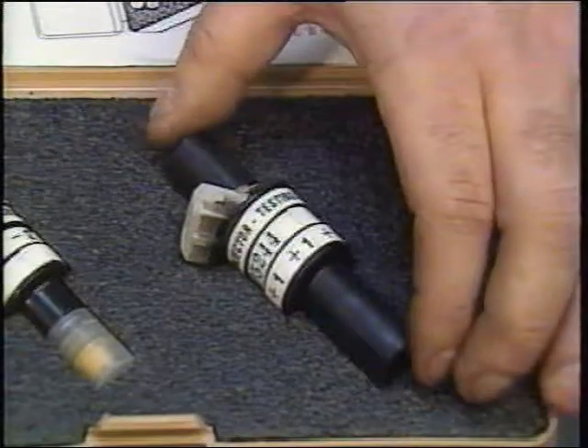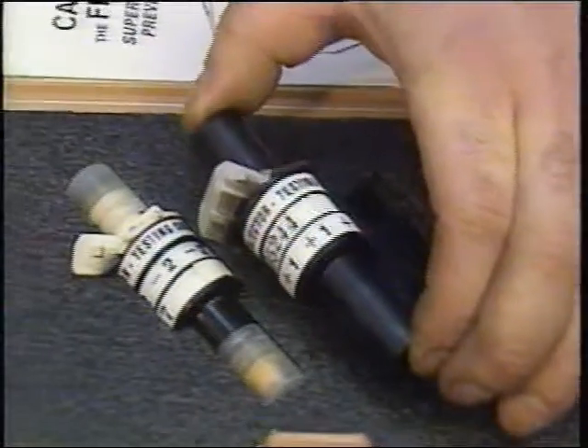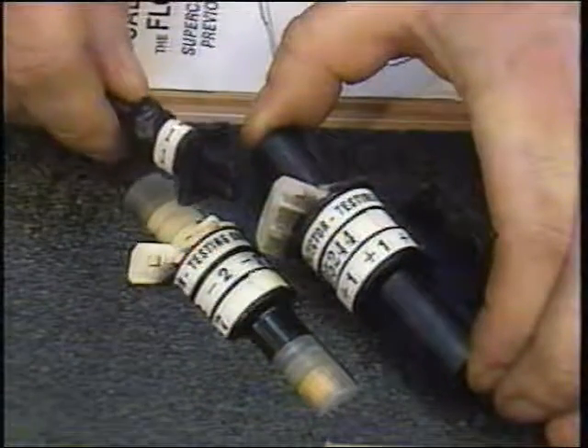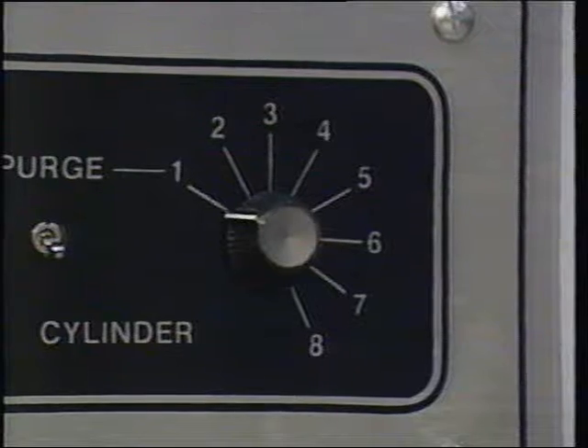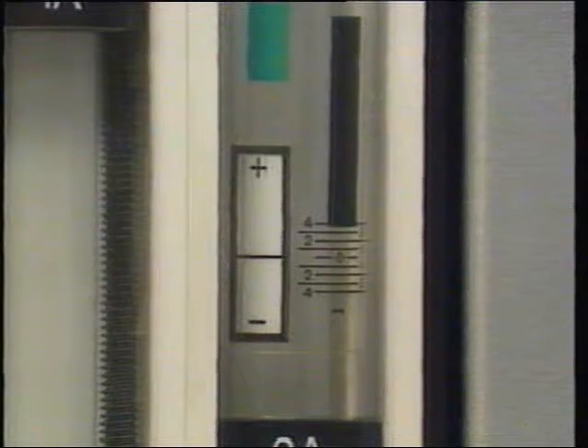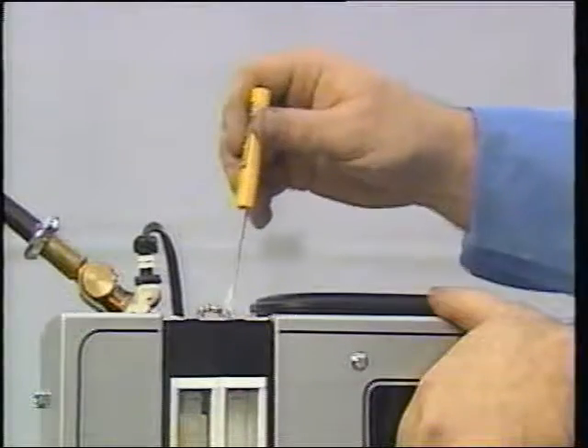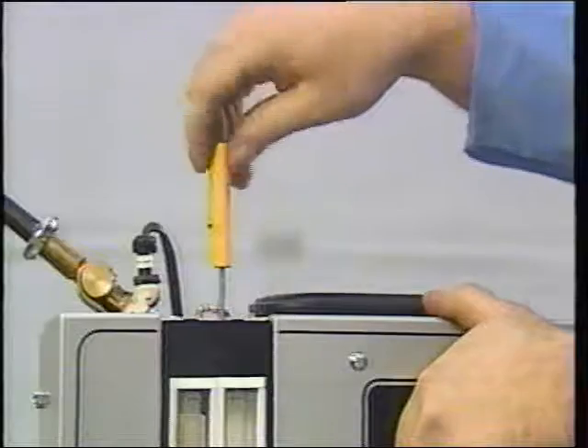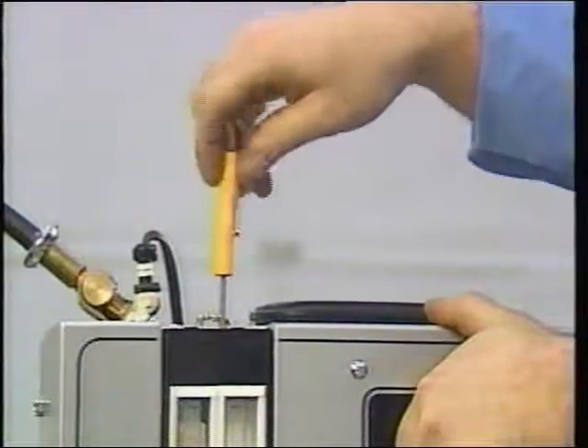There is a separate calibration injector for each flow meter. Use the number 1 harness to connect the injector. The injector selector switch should be in the number 1 position. If the float ball is off the calibration line, the span tube has to be adjusted. You do that by inserting a small screwdriver into the holes at the top of each flow meter and making an adjustment.